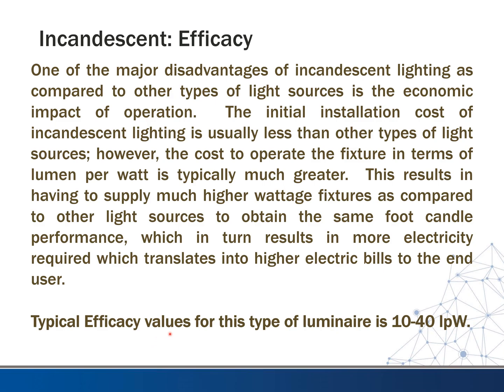Typical efficacy values for this type of luminaire are 10 to 40 lumens per watt. We looked at the table of this in a previous video, and as we saw, this was pretty low compared to other light fixture or bulb types.